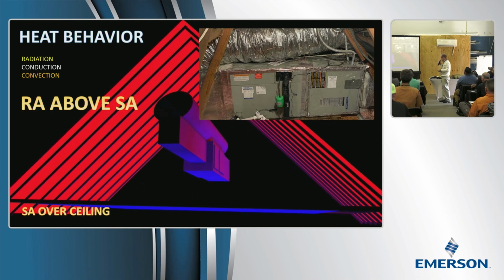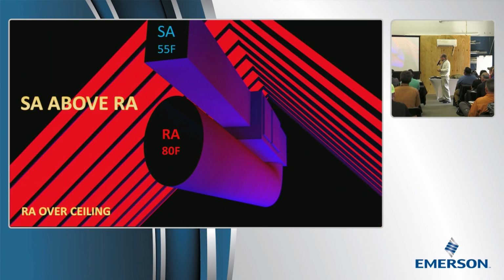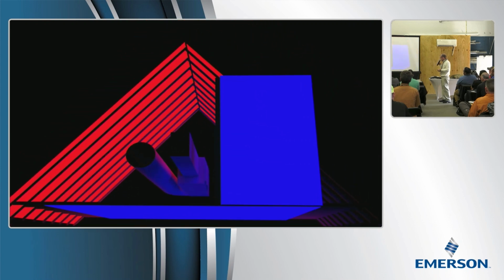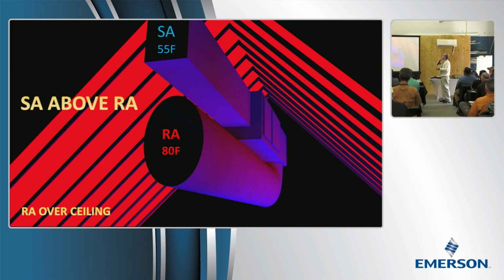If you put the supply air duct on the top, which is the one you're worried about sweating, you can't obstruct the heat from the roof. If you put the return air duct over the top of the supply air duct, it can shade the radiant heat. Or if you put any duct across the top of the air handler, you're shading it. Radiant heat works just like shade. So there's a lot of merit for hanging ducts very high, hanging air handlers on threaded rod, trapeze hangers, getting them up off the cold deck, and putting the warmer duct up top.